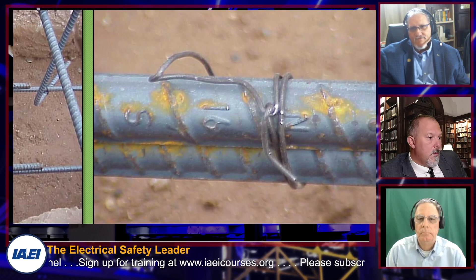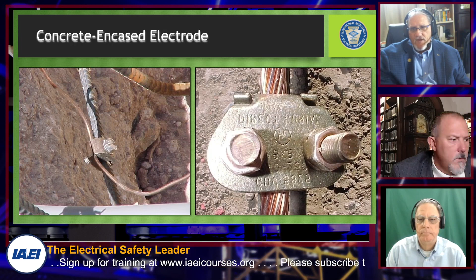If you keep going through to the next couple of slides, it talks about your connectors having to be identified and listed for direct burial concrete encasement. Then the next slide gets into the vertically positioned concrete encased electrode, which has not always been recognized by the code.